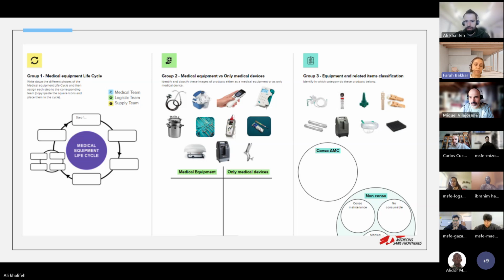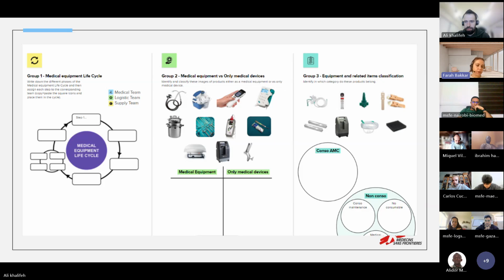Yes, the sensor used per patient, this one is consumable. And the sieve bed is a maintenance spare part. The concentrator is a maintenance spare part. No, sorry, I mean medical equipment. I'm sorry, maintenance spare part didn't make sense. The nasal oxygen cannula is consumable AMC, and the last one, the dust filter of the oxygen concentrator, is consumable maintenance, and it needs to be replaced regularly. That's it.